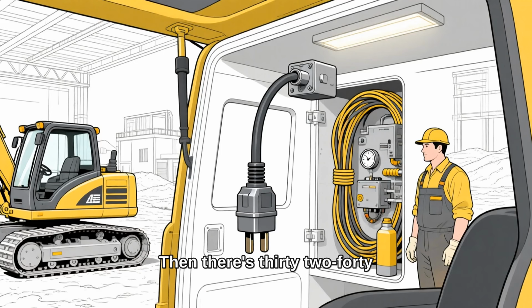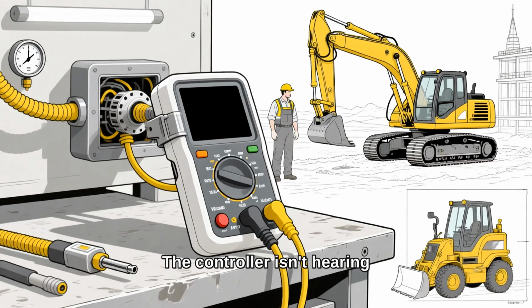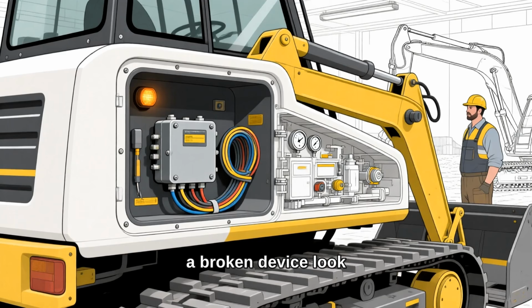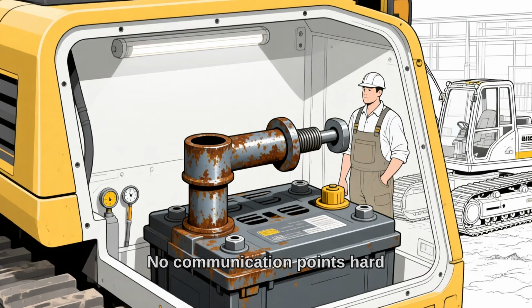Then there's 3241, no communication. Nothing subtle about that one at all. The controller isn't hearing the piece it expects to hear. Not a bad reading. No reading whatsoever. A silent device and a broken device look completely different on a panel, and they get fixed completely differently. No communication points hard at connections and power long before it points at the part itself.